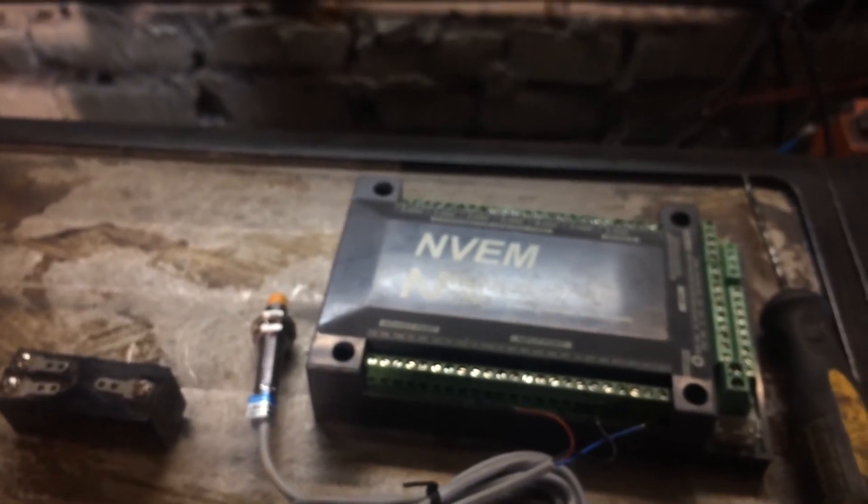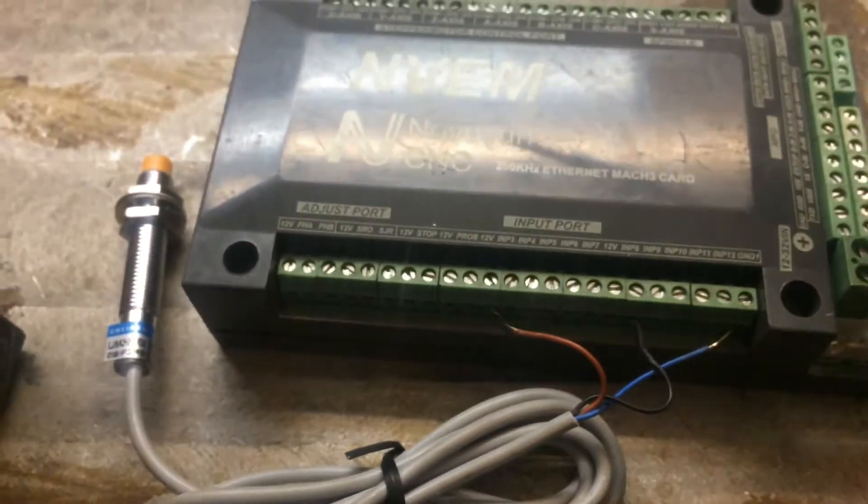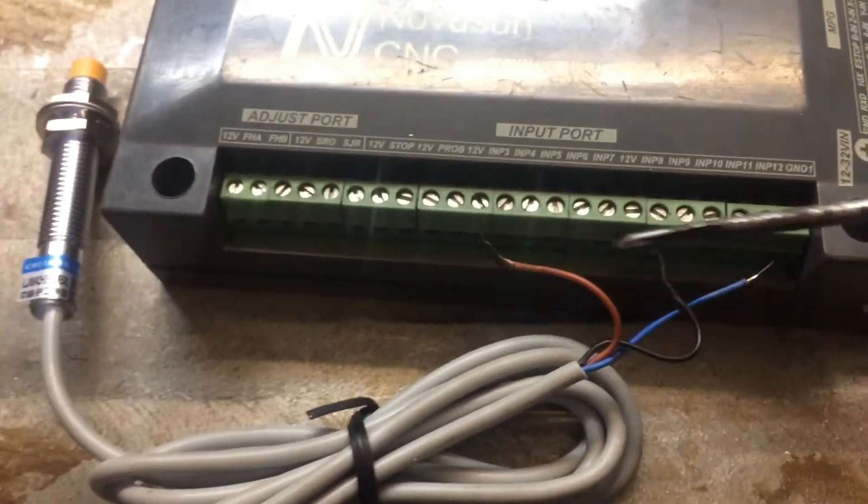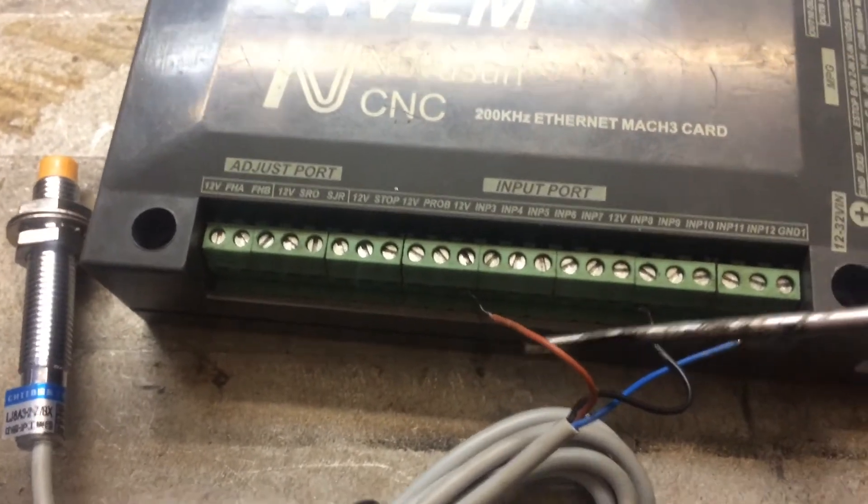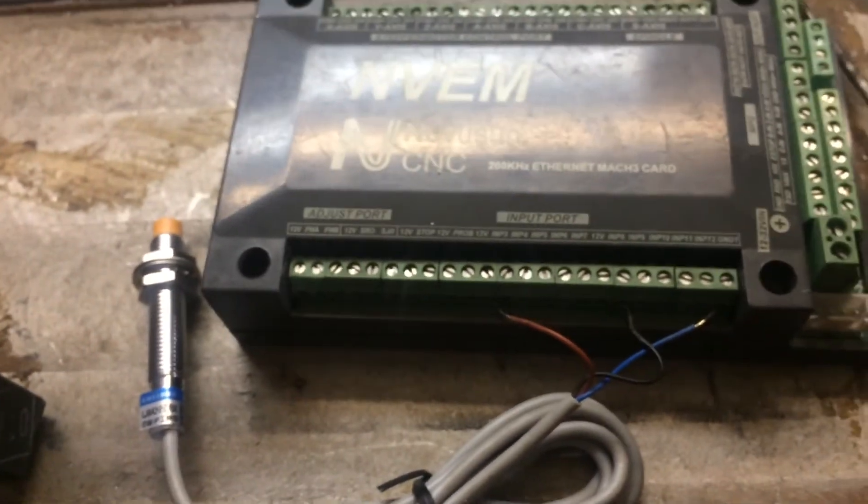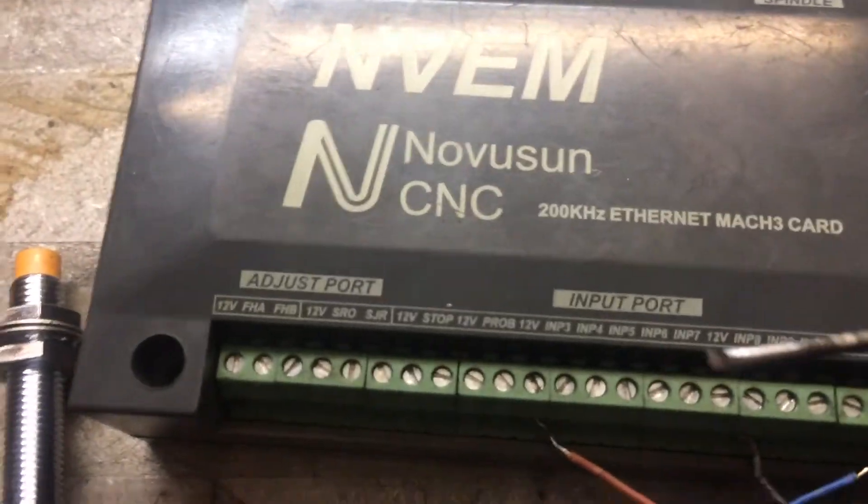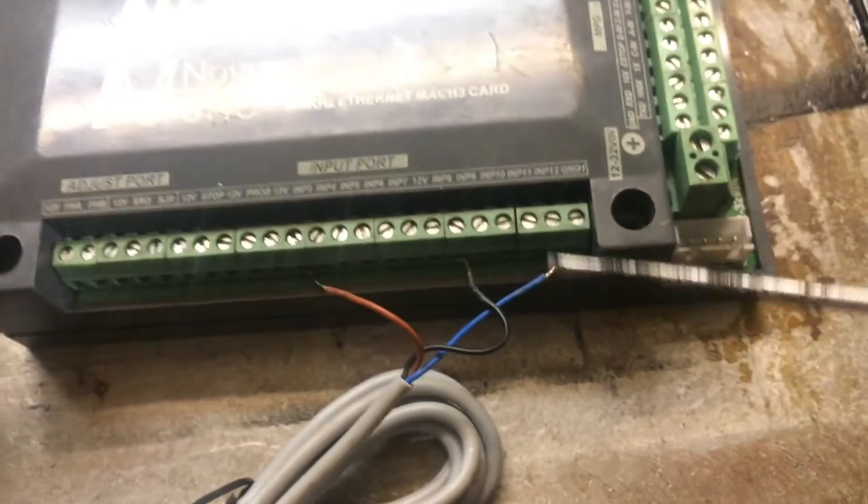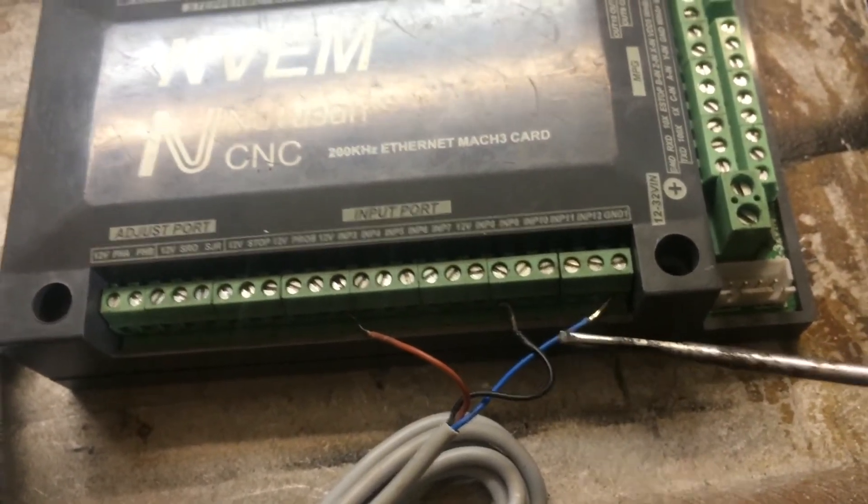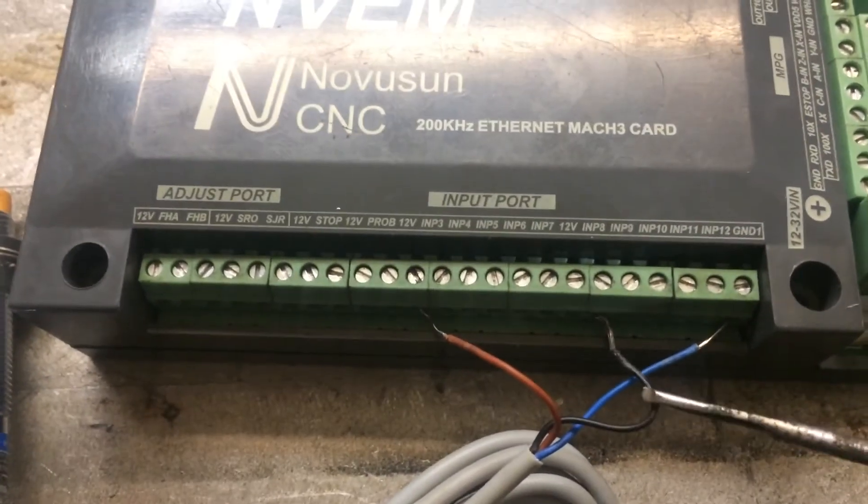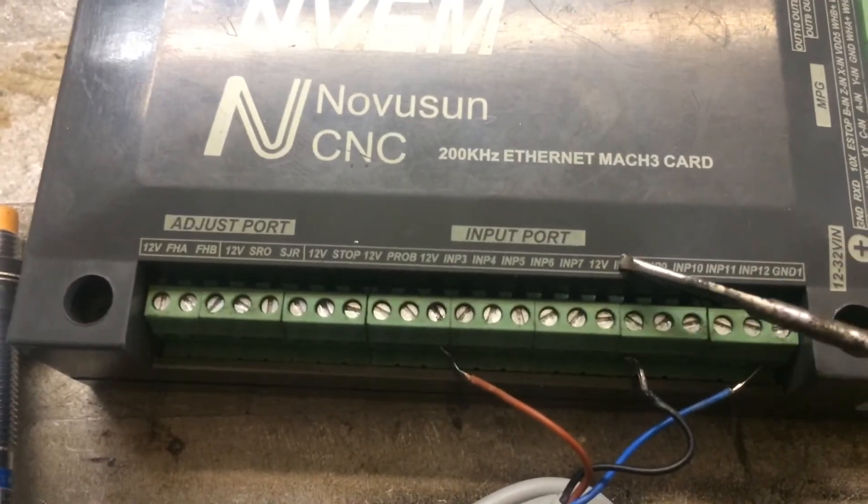So, you need to connect the sensor as follows. The sensor power wire, usually it has a brown color, not always but usually, connected to the 12V port. The terminal, the blue wire, you connect with GND1. And the signal wire, black, you connect with input number 9 as I told.